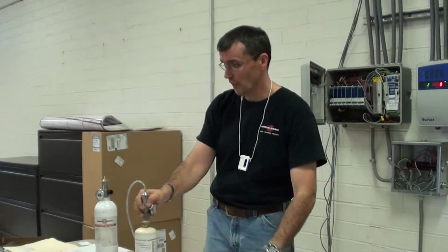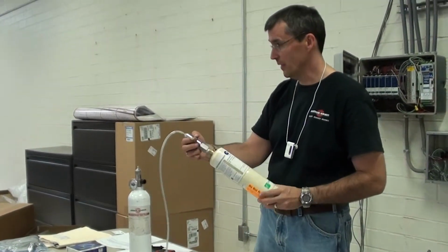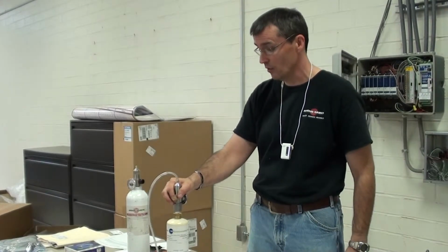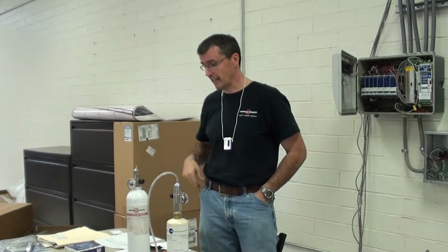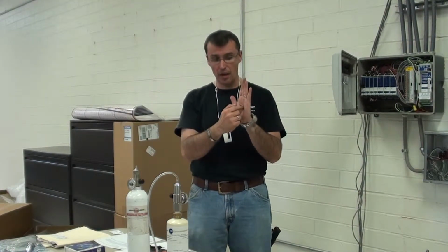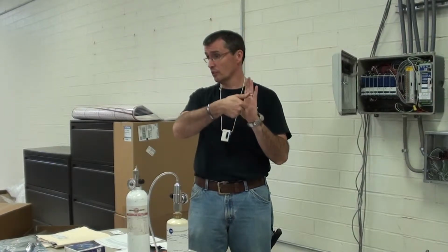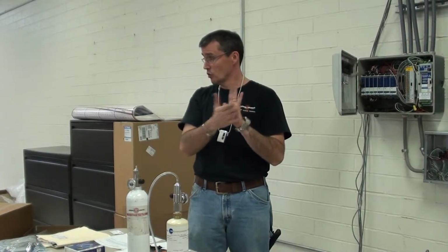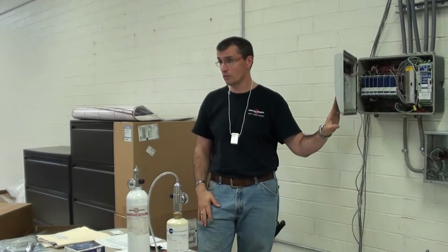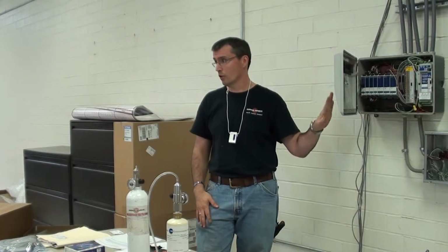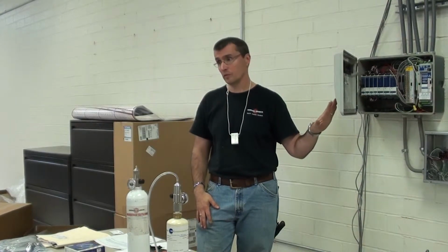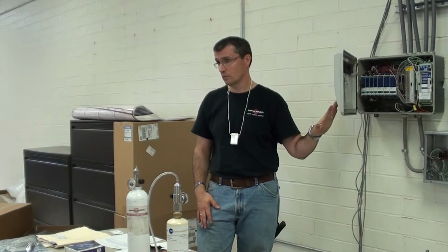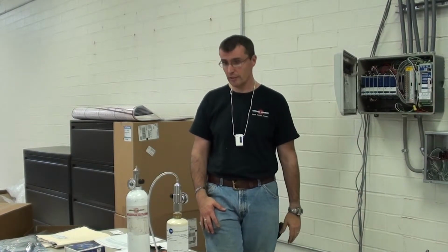So if you're using, again in our case, 50% LEL pentane set for 35% LEL, you're going to set your output for 96 millivolts. At 96 millivolts, if you're not reading dead on 96, you get in that cal potentiometer and adjust it clockwise to increase it, counterclockwise to decrease it. Once you get to 96 millivolts, you'll have someone verify that you're reading 35% LEL at the controller. Okay. And that is a full-blown calibration that you just performed. Any questions? All right, so that's calibration.